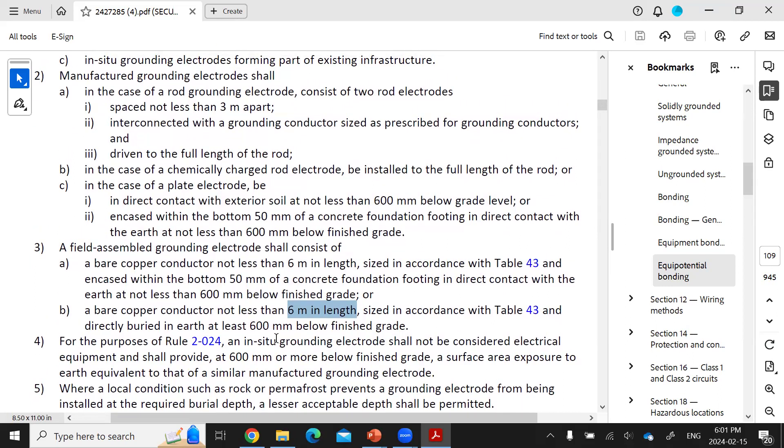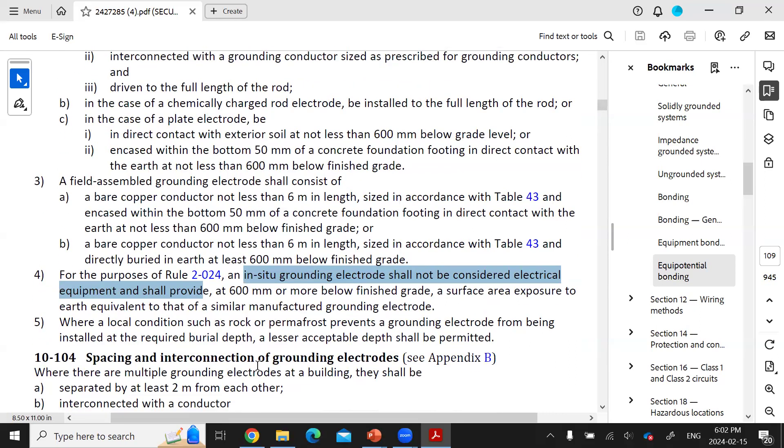Subsection 4 says when a bare copper conductor is buried into an in-situ electrode that is not considered electrical equipment, for example a pipe or a steel line, then the bare copper conductor must be sized in accordance with Table 43 again, and it can be no less than 6 meters long and has to be no less than 600 millimeters below grade again.